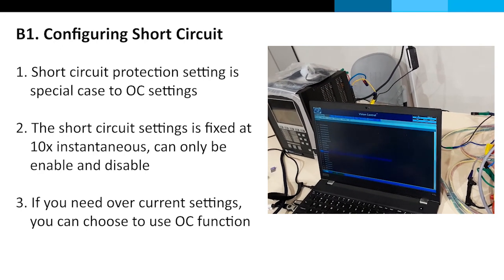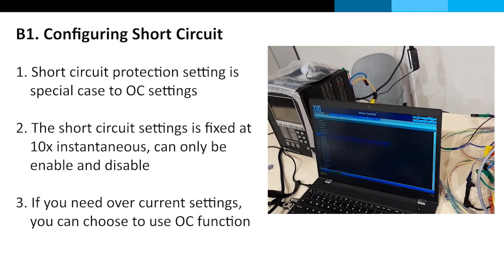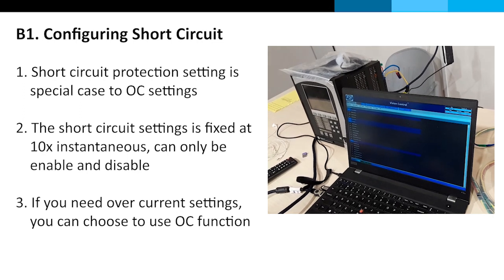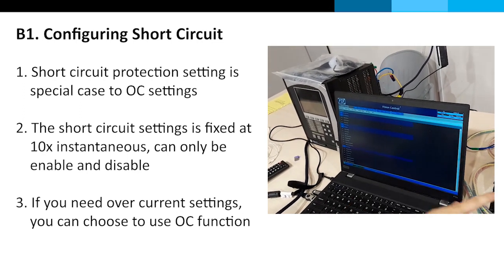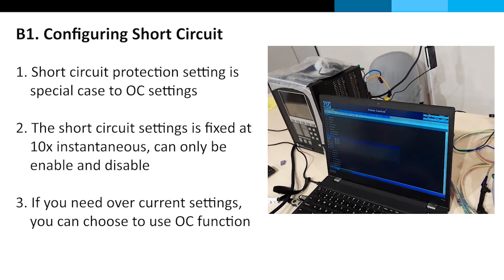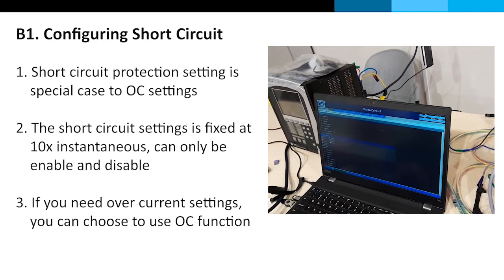There is another one, short circuit high set. Short circuit high set only. High set, but it's fixed at 10 times. Oh, it's fixed, is it? Okay. Yeah, for this usually it is fixed. So the tripping is instantaneous. So you only enable or disable. And the tripping is instantaneous? Yes, less than 100 millisecond. So it's either on or off. Yeah.